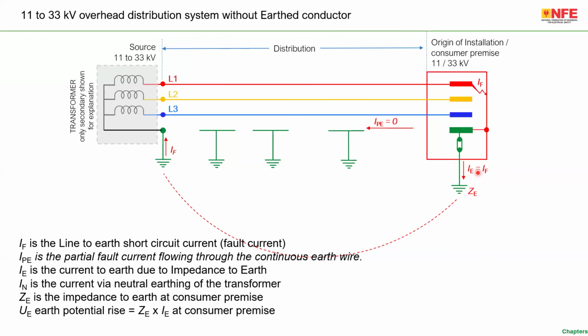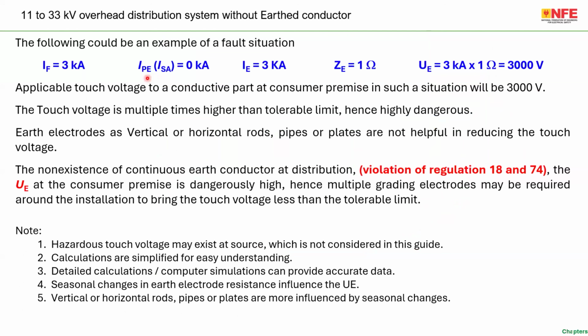Of course, there is inherent resistance of the earth electrode at location B and inherent resistance of the earth electrode at station number A. Since the current is flowing through these earth electrodes, the fault current IF itself will be very much reduced. It will not be 10 kiloampere or 15 kiloampere, that is never going to come. It will be a much lower value.